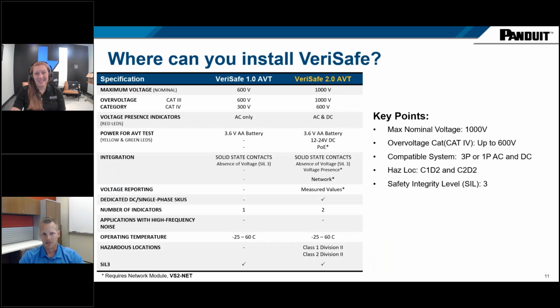So where can you install VeriSafe, right? I'm not going to run through those spec points on the left so much. Those are there for you to read through once you get the presentation later. But the key points I want to cover are max nominal voltage up to 1,000 volts. Cat 4 is up to 600 volts, so you can get into those service entrances, those 480 service entrances. Compatible systems: 3-phase, single-phase, AC or DC. We have all those compatibilities with VeriSafe. And C1, D2 and C2, D2 hazardous location ratings as well.